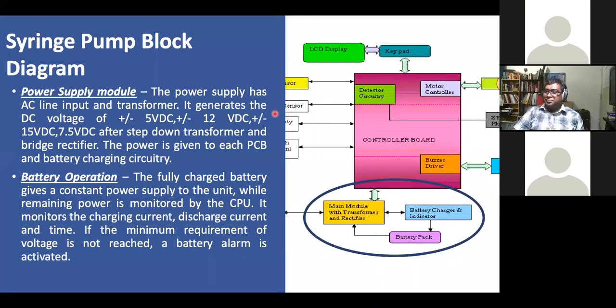Power supply and battery operation are very important. The power supply is going to charge the battery and send supply to the circuit. The battery plays a very important role because for an infusion device or syringe pump, you need to have a backup battery. If anything goes wrong with your power supply, the backup battery is going to work and keep the infusion or the syringe pump running.